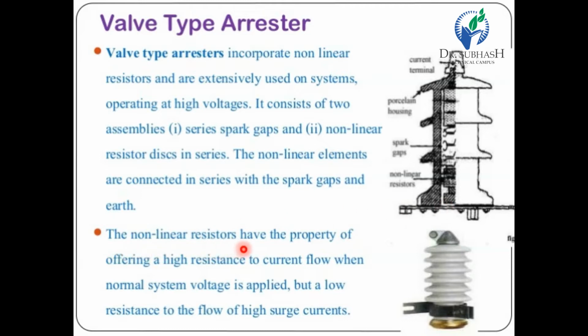The non-linear resistors have the property of offering a high resistance to current flow when normal system voltage is applied, but a low resistance to the flow of high surge currents. This is the property of a non-linear resistor, and we use this property in valve type arrestors. This is the image of a typical valve type arrestor.